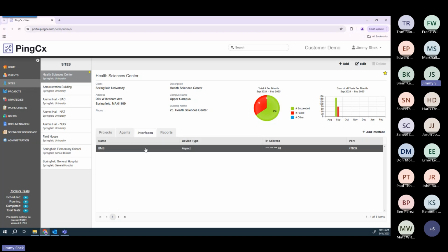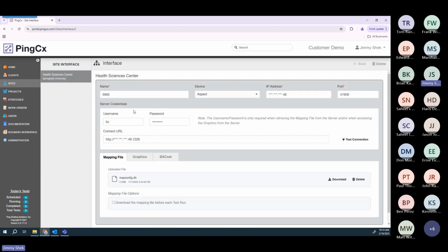On the site level is where you define the interface. The interface essentially acts as the communication layer between PingCx and the BMS backend system. We support various platforms and devices, whether it's an Aspect, JACE, web, or even standard BACnet routers. You essentially specify the IP address and port that you use to communicate. We also have the ability to take screenshots of the BMS system. So here's where you would specify the credentials and the connection URL.